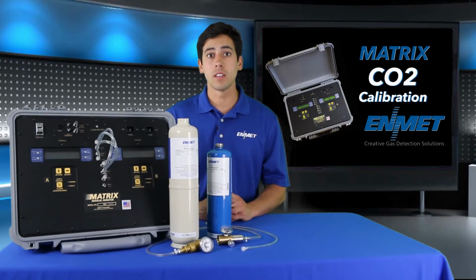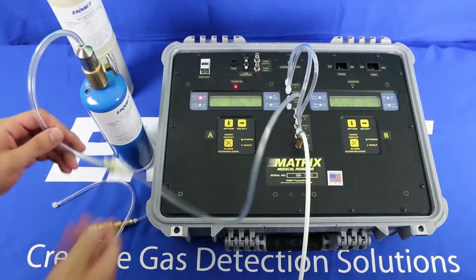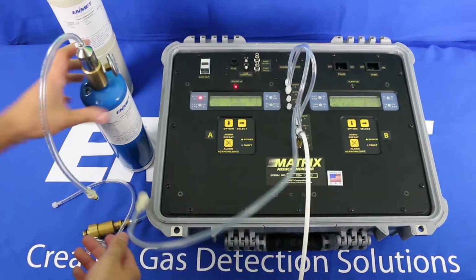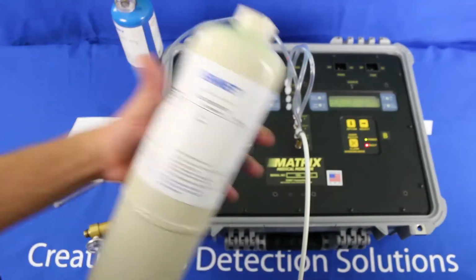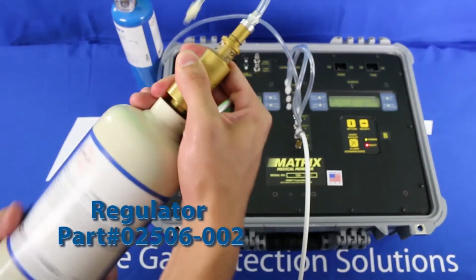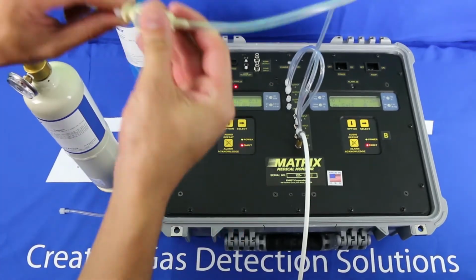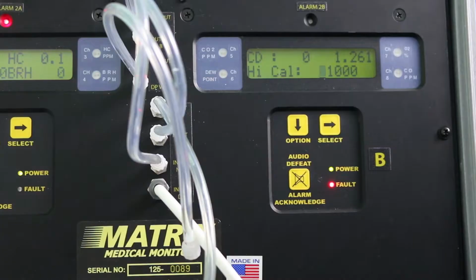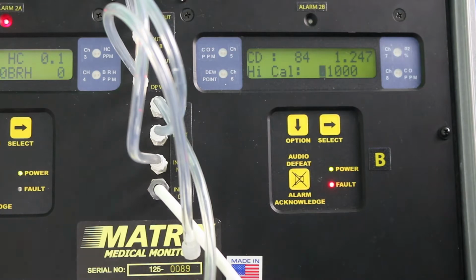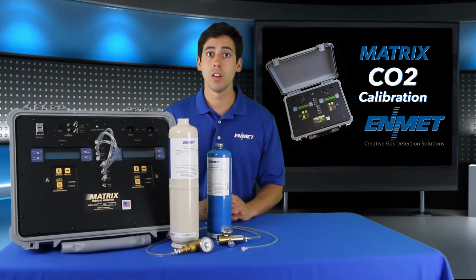After pressing Select, you need to supply the 1000 ppm CO2. To do this, you'll need to close the valve on the regulator and disconnect the O2 gas. Now you may attach the CO2. The present CO2 value should now be increasing and the voltage output will be decreasing. The factory preset for your instrument should be 1000. Once the sensor is stabilized to the point where it isn't drastically changing, you can accept the cal.